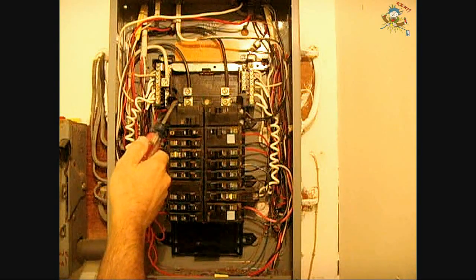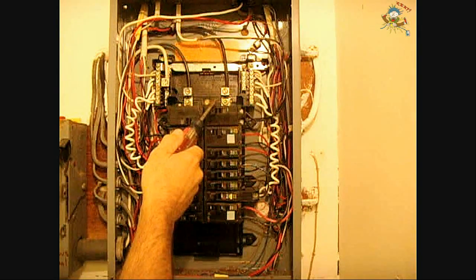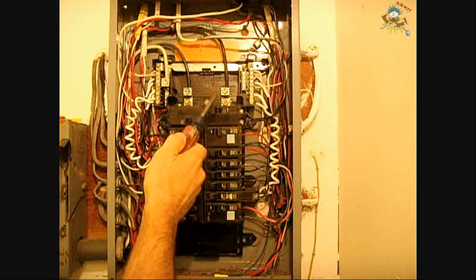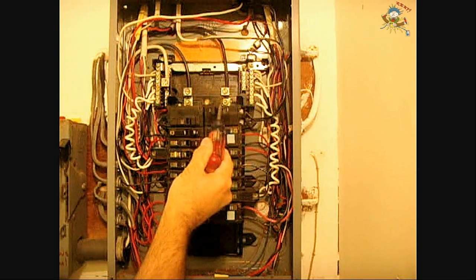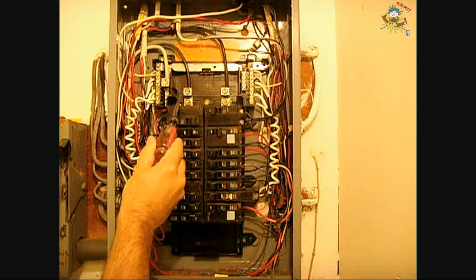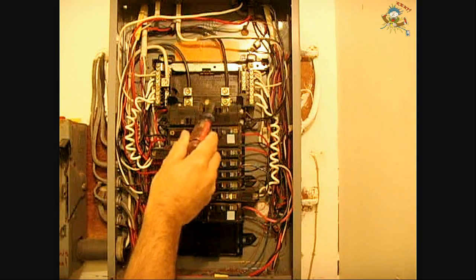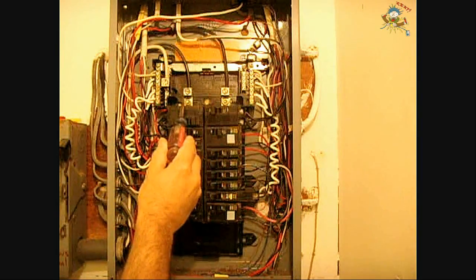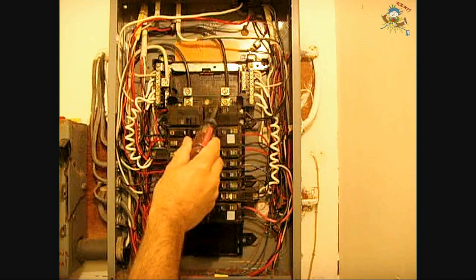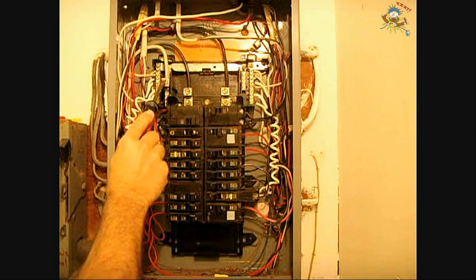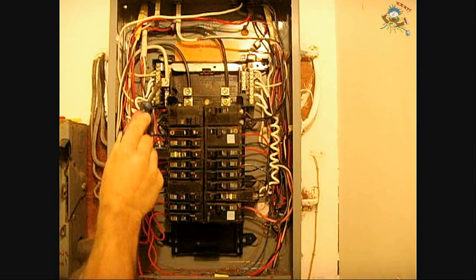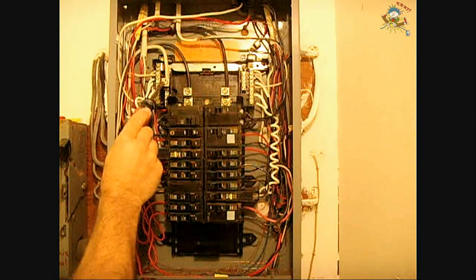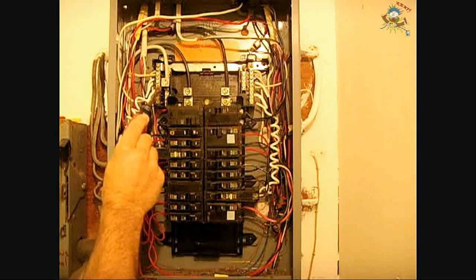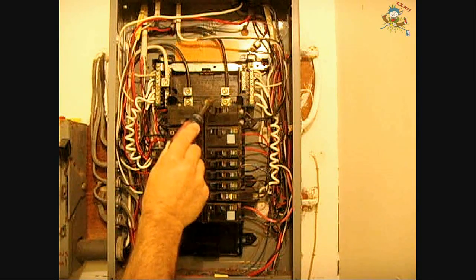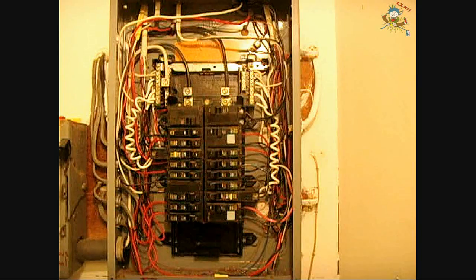It's rated at 100 amps. You can see you have two lugs. That's a hot line coming in. That's your other hot line coming in. If this was a three-phase panel, you would see not just that hot lug and not just that one. You would have a third one. Each one of these is 120 volt potential. So between that lug and the neutral or ground, which is right here, you have 120 volts. And from this lug here to that terminal, you also have 120 volts. Between the two together, you would have 240 volts.